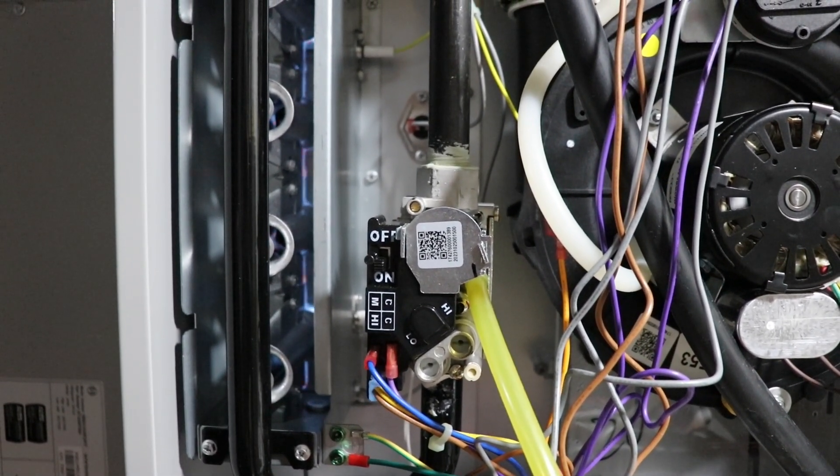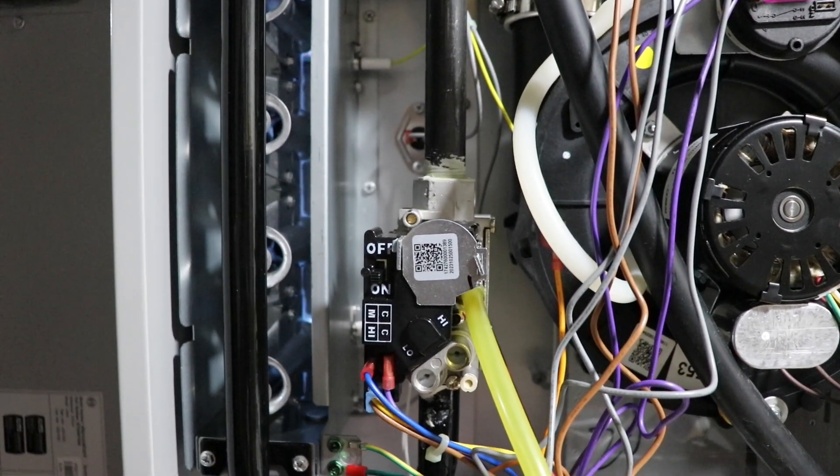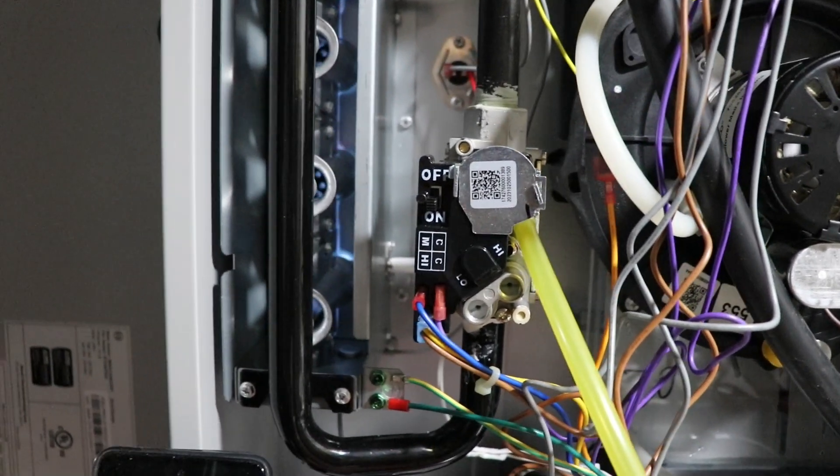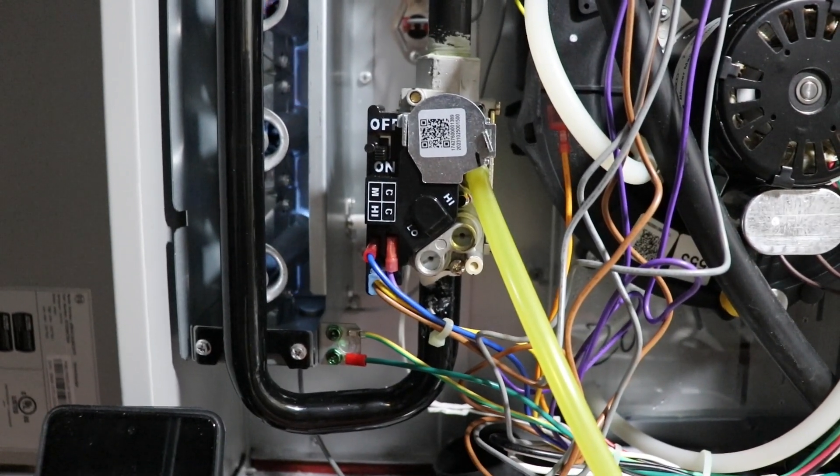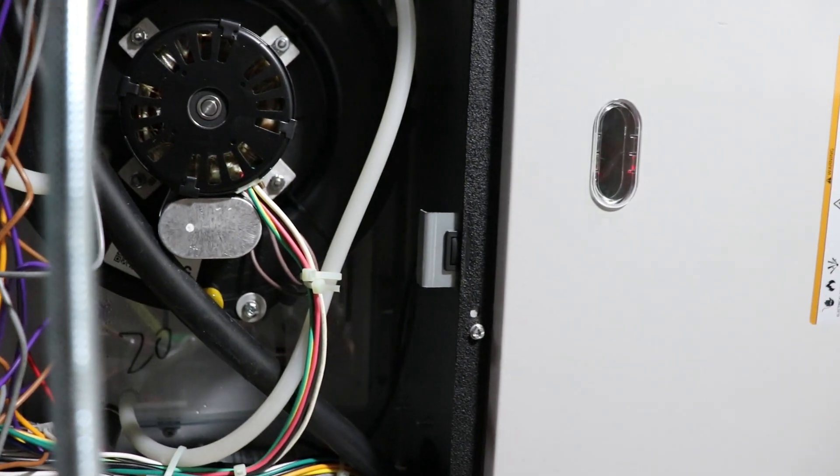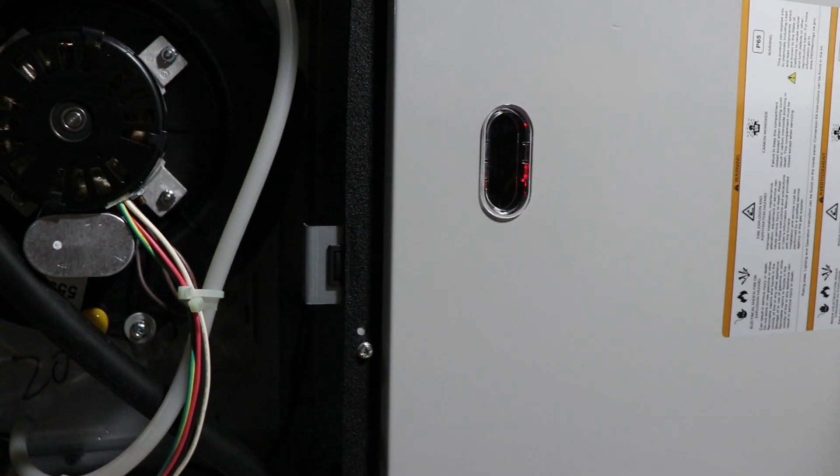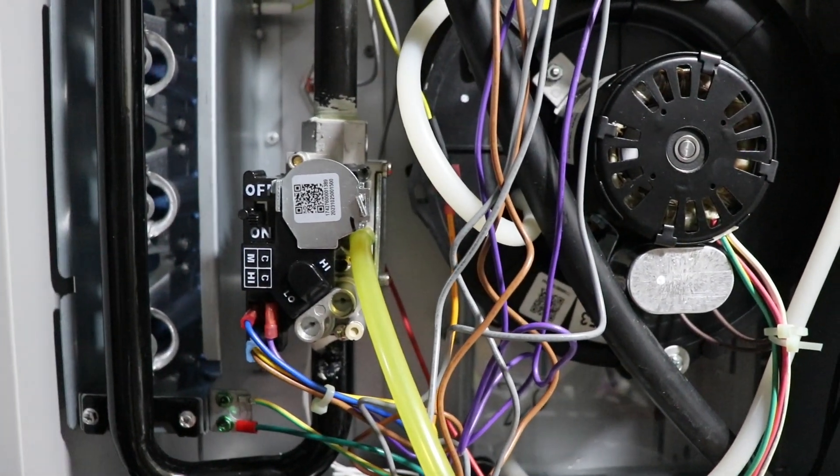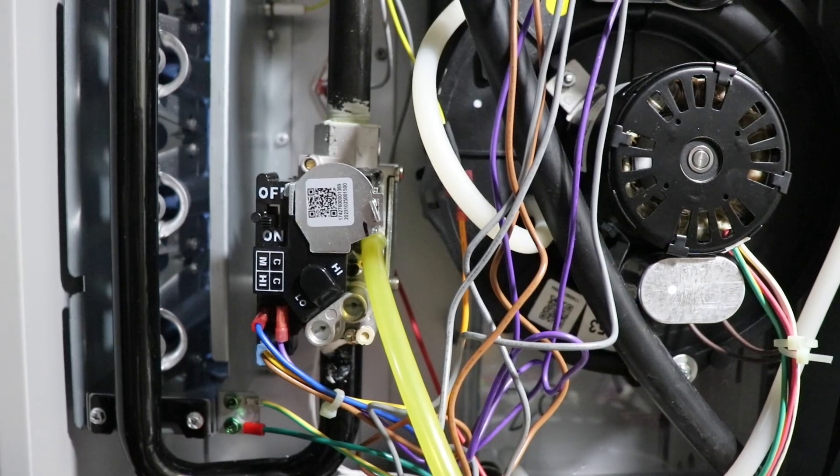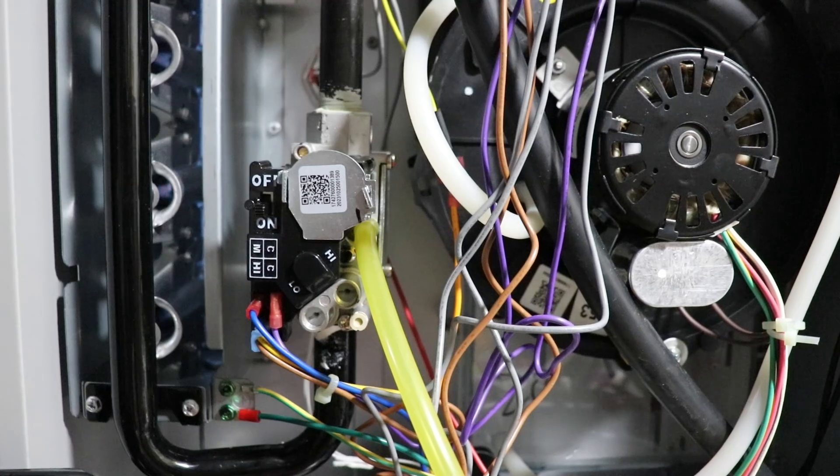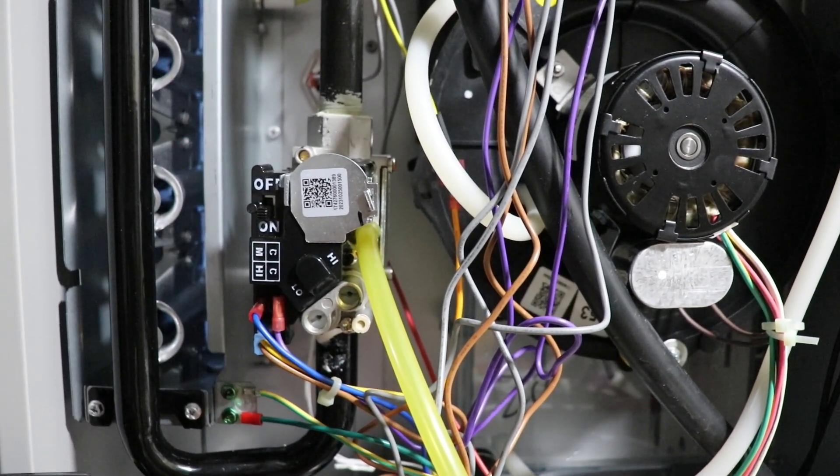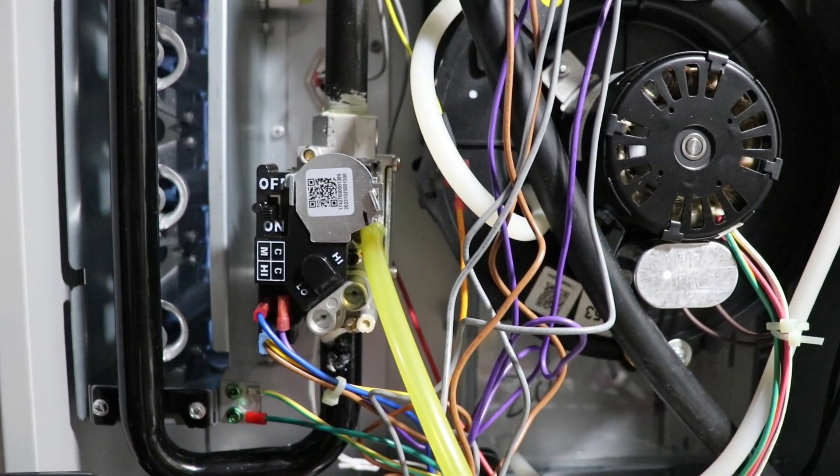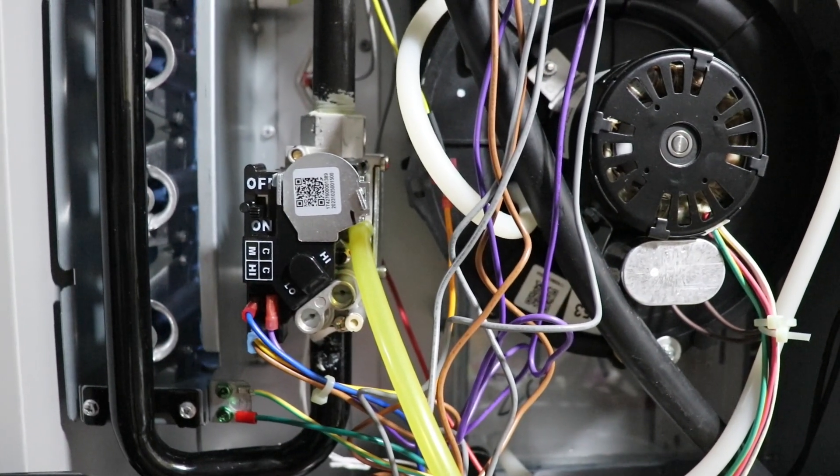We'll talk about maybe analyzing the data from the Ecobee afterwards. Basically what will happen is the furnace will run in H2 for a length of time if it's firing too hard. It'll trip out on the furnace side, but the thermostat is continuing to call for heat. The indoor temperature keeps falling. It'll fall for, I don't know, half an hour to an hour before the furnace successfully restarts, and it'll climb up again. Hopefully you reach set point at that point, but you may not. So you end up with continually losing temperature inside of the home.